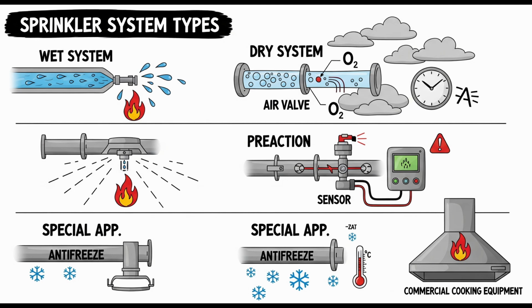supply for maintenance. Is a relief valve needed on the air supply line itself before it gets to the system? Yes. An approved relief valve is required between the air supply source, like the compressor, and that shutoff valve. It's set to relieve pressure at least 10 psi above the normal system air pressure, but it can't exceed the air supply equipment manufacturer's limits. This protects the air supply components, compressor, receiver, etc., from overpressure. Makes sense. Protection for the equipment.